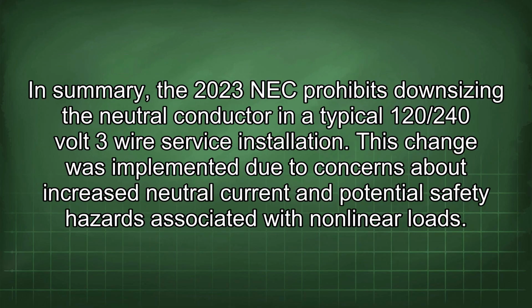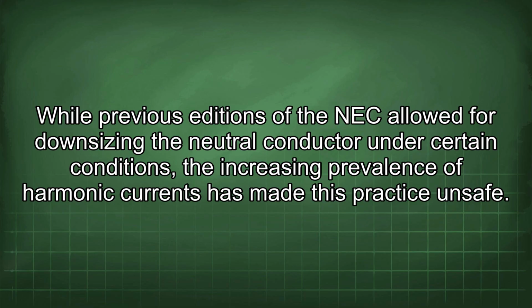In summary, the 2023 NEC prohibits downsizing the neutral conductor in a typical 120/240 volt 3-wire service installation. This change was implemented due to concerns about increased neutral current and potential safety hazards associated with nonlinear loads. While previous editions of the NEC allowed for downsizing the neutral conductor under certain conditions, the increasing prevalence of harmonic currents has made this practice unsafe.